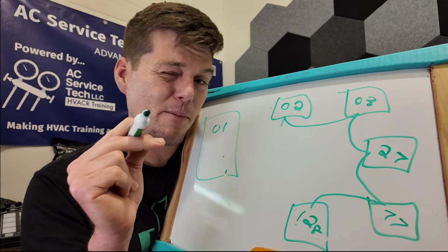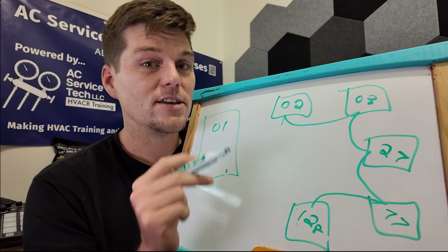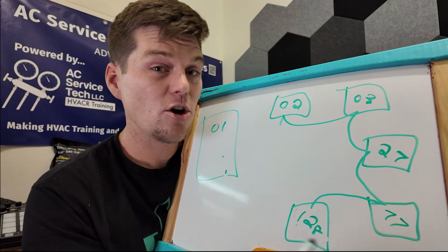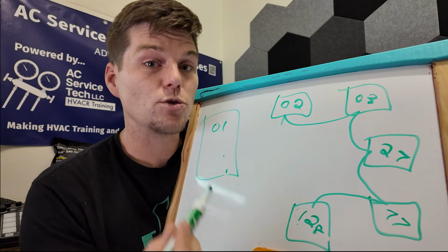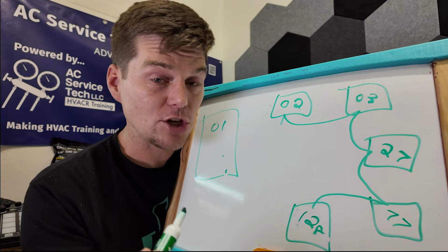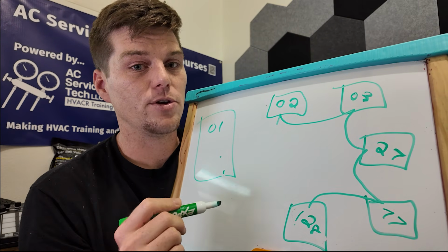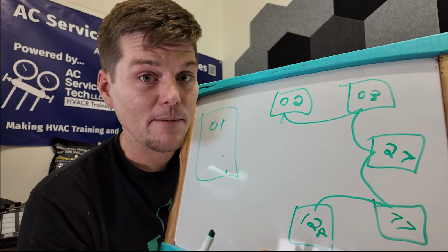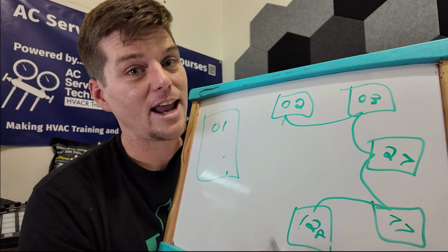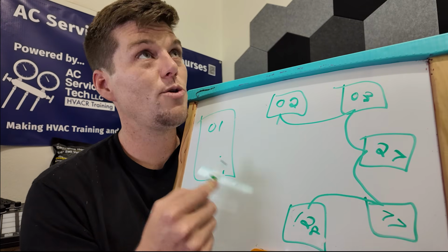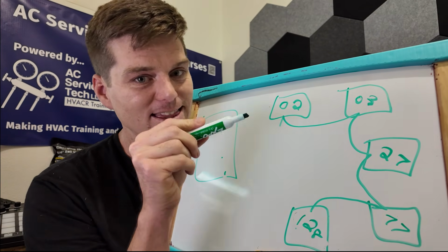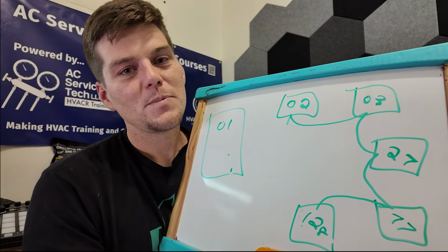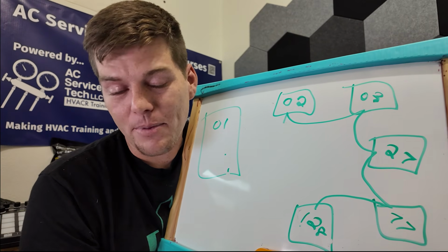Now, if you've read my A1P board troubleshooting guide, you'll know that when you reset a unit on power cycle, especially when you hold the reset or cause it to auto address, the DC voltage will turn on and off randomly, trying to count and communicate with indoor units. So it's going to be on, off, on, off. Now that's not a bad board. That just means that you reset the unit and now you have to wait for it to initialize, tell you you have a U4, then stabilize and send the 16.5 volts DC you're looking for. So it is kind of a time waster in my opinion.